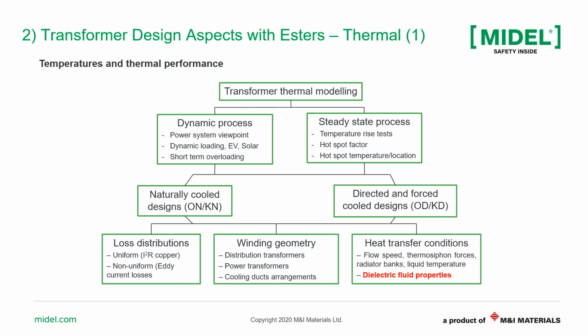The dynamic side of the thermal modeling is really dependent on the power system viewpoint. So you can have dynamic loading because of extra electric vehicles on the grid or solar panel generation, and this could lead to short-term overloading. Once we look at these two, either steady state or dynamics, we need to know what is the transformer cooling mode. So natural cooled transformers are different from directed cooled transformers and forced with pumps. So when we talk about thermal, we need to understand: are we talking about steady state? Are we talking about dynamic? What is the cooling mode of the transformer? Is it natural cooling or directed cooling?